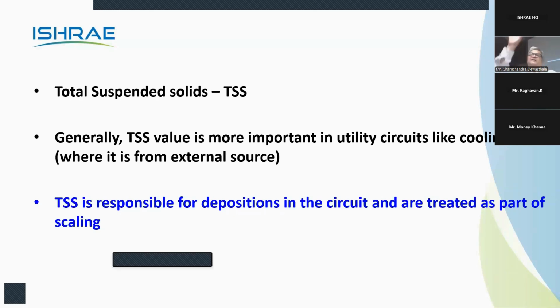Now, when the cooling tower sucks fresh air from the terrace, what it sucks is all this dirt, dust, unburnt carbon, gases, everything. It sucks and puts it into the cooling water. Now two problems arise. The TSS value of Vapi cooling waters is very high. This is one. And second is pH is always suppressed, because they are putting more acidity into the cooling water due to CO2 which is getting dissolved, and they have a problem of corrosion in the system.